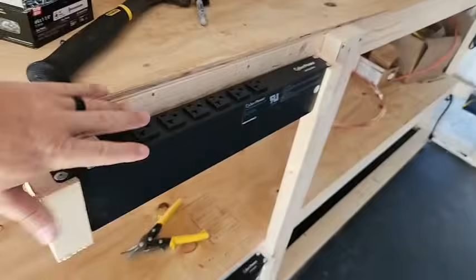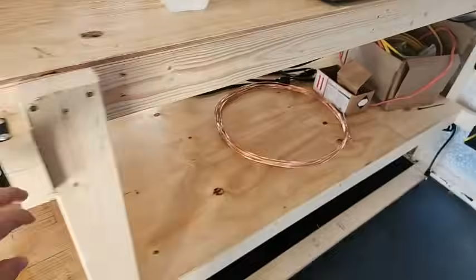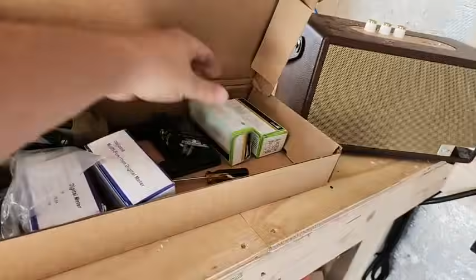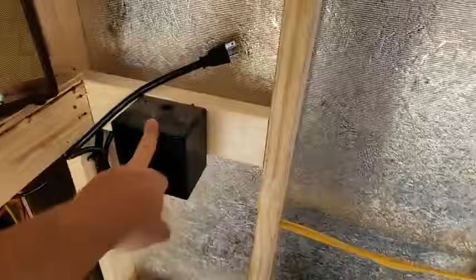Joey was just adding these - these are the PDUs I decided to go with for the fans. They're made by CyberPower, a little better quality. 20 amp runs, so those get installed and run all the way over to the meter box over here. This is one of the things electricians have to finish. These will get the DROK meters, and these are just traditional outlets, which will be perfect because then we can monitor the watt usage for the actual fans. That was something I had issues with some time ago, so we'll actually be able to monitor that, which will be nice.